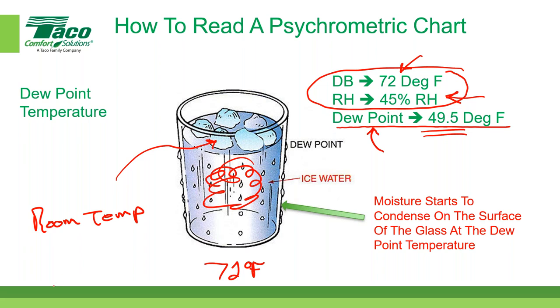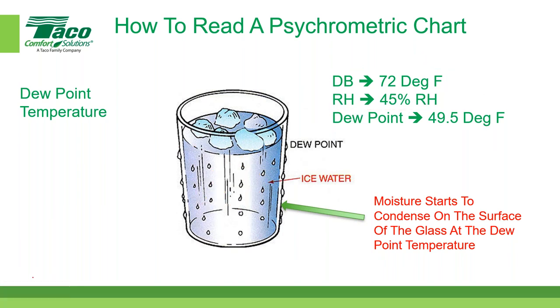So far we've talked about wet bulb temperature, dry bulb temperature, and dew point temperature. Hopefully that gets us focused on what those three values are. Whenever we're talking about air, the room that you're sitting in right now, those three values are constantly floating around in terms of HVAC systems. At any one moment, wherever you're sitting, you have the dry bulb temperature, which you can measure with a conventional thermometer. You have the wet bulb temperature, which we showed you how to measure. And you have the dew point temperature. As it turns out, you only need two of those values to use a psychrometric chart, which we're going to get into next. Any questions, Brett, about those three?